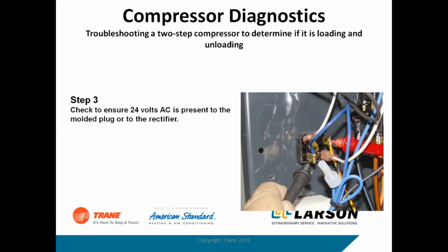Because if you do short out the wires to the rectifier, it could be a bad rectifier. It could be a short in the solenoid in the head of the compressor also. And by the way, if the rectifier is bad, not a big deal. You just get a new rectifier, put it in there, and you're good to go. If the solenoid shorts out, you have two choices. You can either change the compressor or just let it run in low stage. But there's no fixing it at that point. Once it burns out, it's a new compressor or run in low stage.